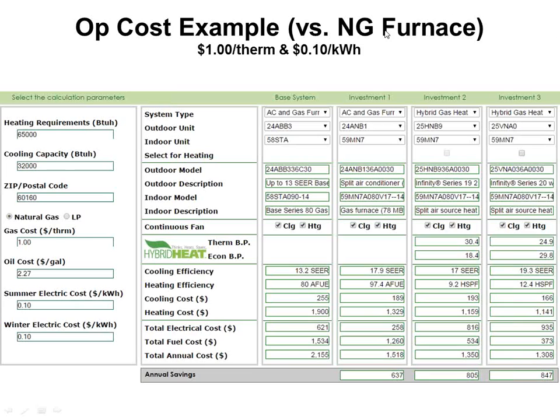So what you do on this particular tool, see if I can get my little red dot back. You put in the heating BTUs. In this case, I got 65,000, cooling 32,000. Zip code, which is my zip code where I'm sitting right now here in the Chicagoland area. I put in my natural gas cost. This particular one was a little bit older, so I had $1 in here.